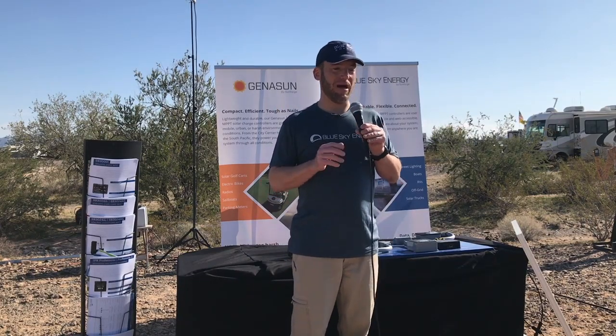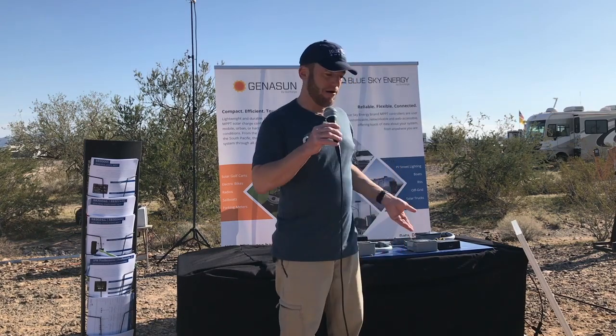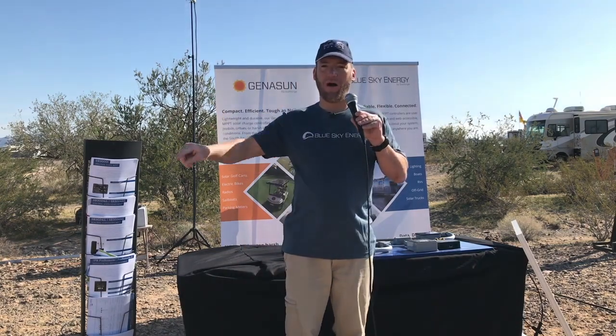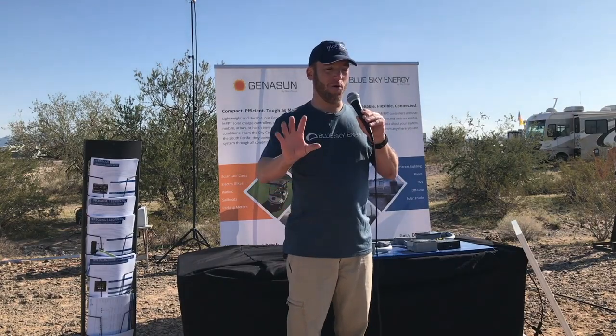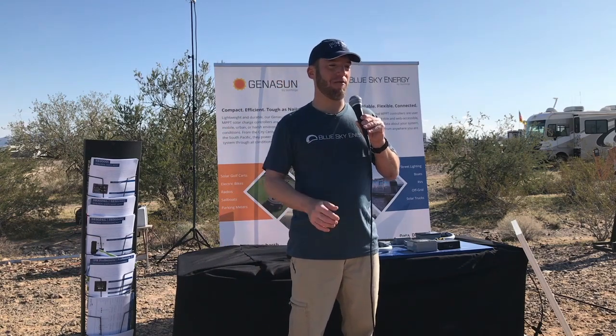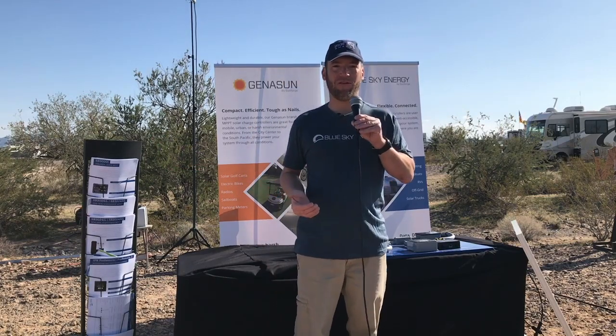With a lithium battery system, if you don't have a battery monitor like our IPN Pro remote with the current shunt, I really recommend one. Lithium battery voltages are very stable, so you don't get much warning before your battery cuts off. It'll read 12.8, 12.8, 12.8, then suddenly off. Unlike a lead acid battery, where you can see it getting down to 12.2 and think, maybe I should turn on the generator. You really want a battery monitor like our IPN Pro remote display that tracks all the current going in and out.